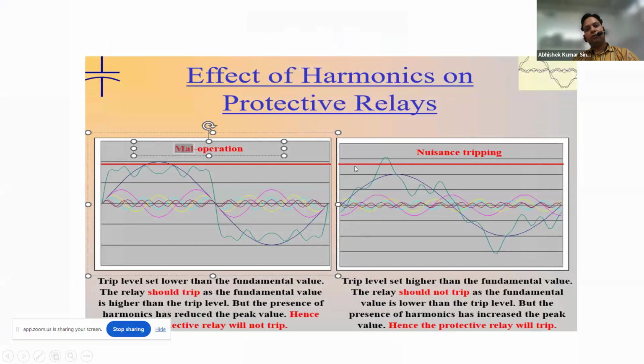Now, the effect of harmonics on protective relays. Suppose we have a fundamental frequency, then we have multiple harmonics, and this is the resultant waveform, which is a combination of the fundamental as well as the harmonics. Now we have set a trip value, that it should trip at this peak value, but due to harmonics, the peak is not coming. Due to this, our breaker or whatever device has to trip will not trip. In this other case, the magnitude is high, so if we have set that we have to trip at this point, it will trip again and again. So this will definitely cause nuisance tripping.